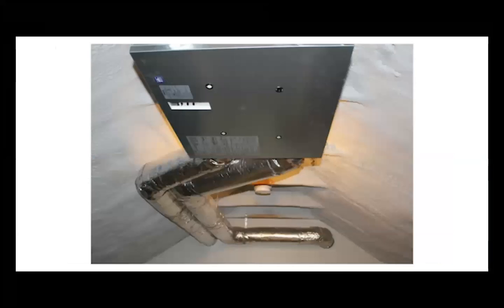We also, in the last house, had added a fresh air damper to operate when the kitchen hood was running. A makeup air damper. And that was a late add, actually, in order to get our LEED certification, because we were just getting too negative. We were going down, even with not very much exhaust flow from the kitchen range hood, with only 175 CFM, we were going down to minus 11 pascals. So we added that damper. So we knew in this house right away that we wanted to address that and make sure that we were going to be able to have balanced ventilation. Although we use the range hood less, simply because in the old house we had gas, so we ran it even when we were baking.